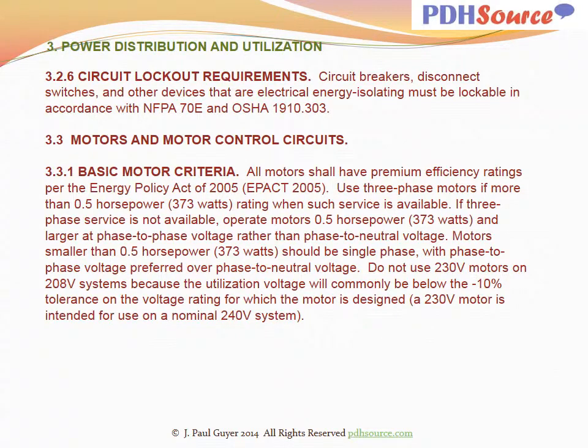Circuit lockout requirements. Circuit breakers, disconnect switches, and other devices that are electrical energy isolating must be lockable in accordance with NFPA 70E and OSHA 1910.303. With regard to motors and motor control circuits, basic motor criteria: all motors shall have premium efficiency ratings per the Energy Policy Act of 2005.